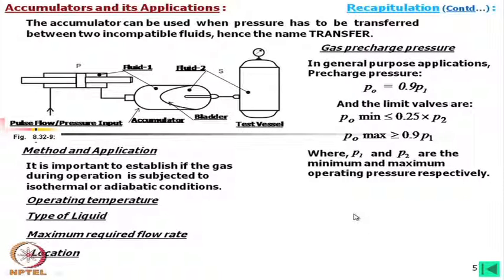It is important to establish whether the gas during operation is subjected to isothermal or adiabatic conditions. If the process is occurring very quickly, we consider adiabatic (isentropic) conditions; if it is slow, isothermal. We have to calculate accordingly. The operating temperature and type of liquid are also important, as is the maximum required flow rate and the location where the accumulator should be placed.